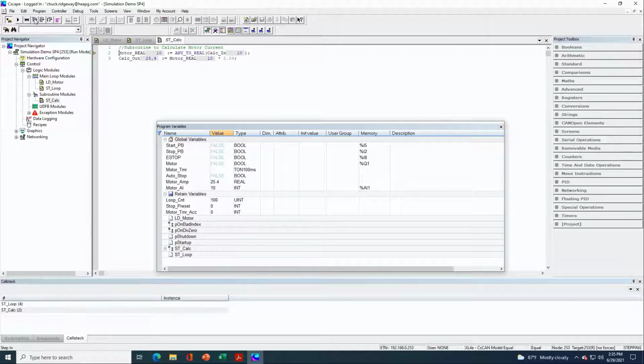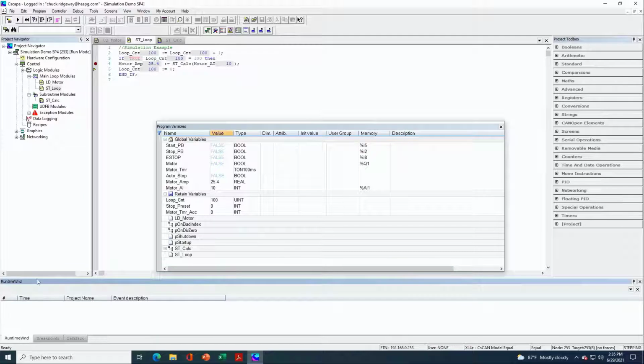As I continue to step through that, you'll see that I go back up to line 5, which is the line after where I called. So the call stack can be really useful, especially if you have multiple levels of routines that you're dealing with. Now the last thing I want to talk about are trace points. Unlike breakpoints, where you pause at that point in the logic, trace points are where you simply make a time and date stamp happen whenever that part of the logic is executed.